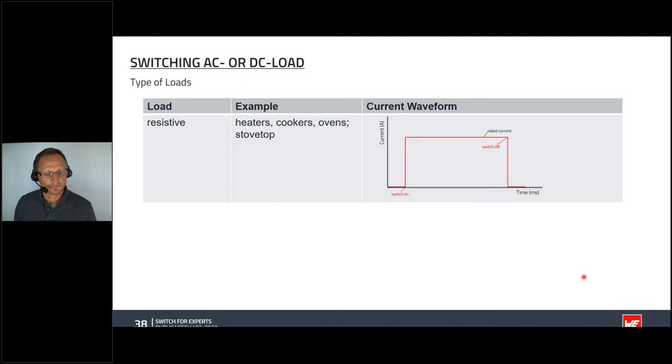There can be, for example, resistive load, like most heater elements. However, during the startup period of many common devices, they show a significant inrush current, which can rise up to multiple times the value of the nominal consumption. Over and above that, this startup period can last from microseconds to milliseconds, up to seconds in some cases.